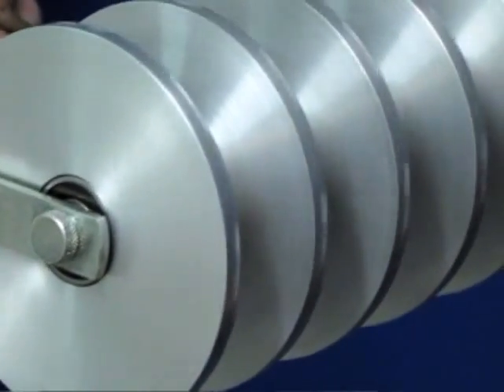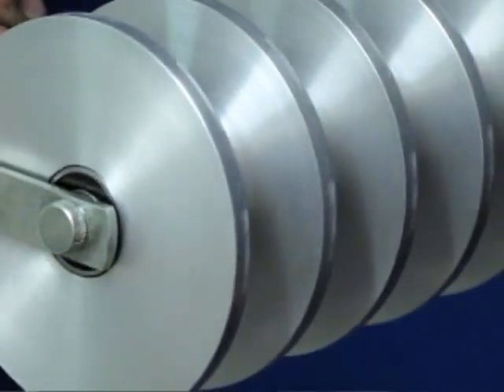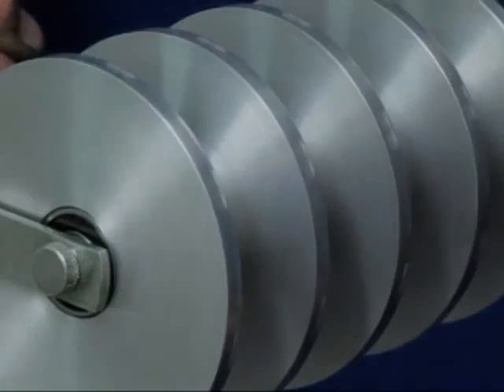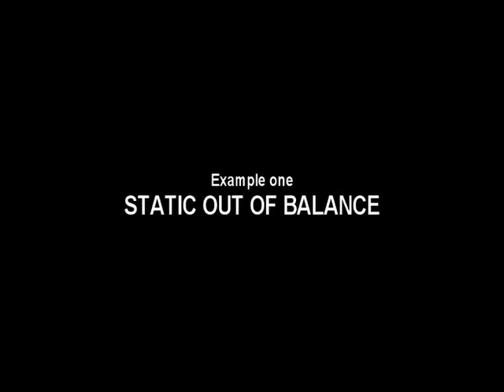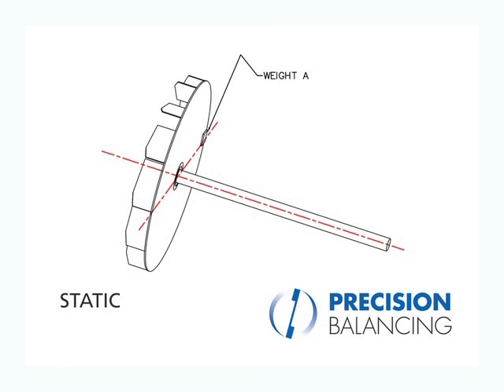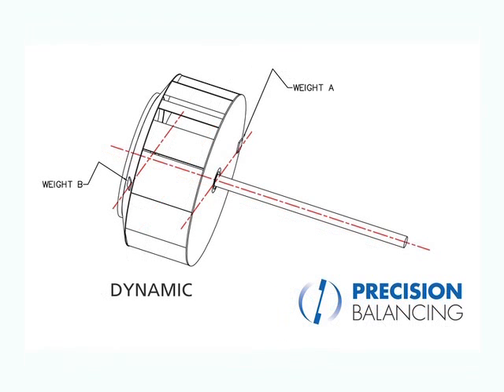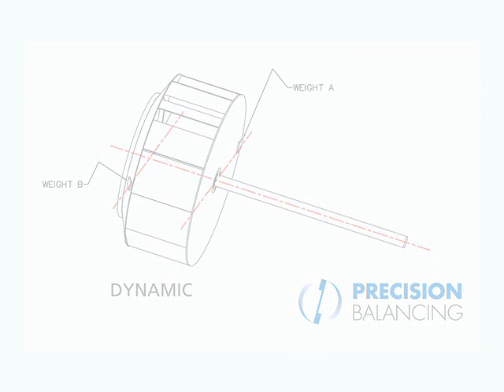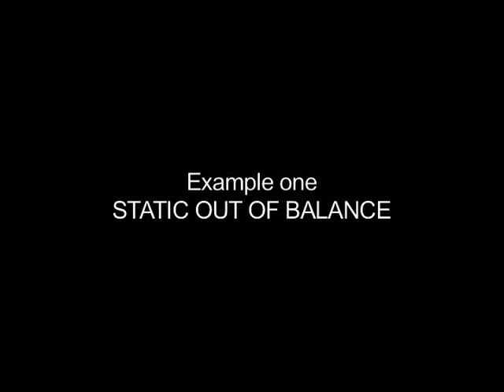Static and dynamic out-of-balance is uneven mass distribution around the rotational axis of the rotating object. Static out-of-balance is uneven mass on the rotating object's axis in a single plane, causing the object to fall to the lowest, heaviest position when it settles at the point of rest. Dynamic out-of-balance is in two planes and can only be detected when the object is rotating and the uneven mass is distributed around the object from one end to the other.